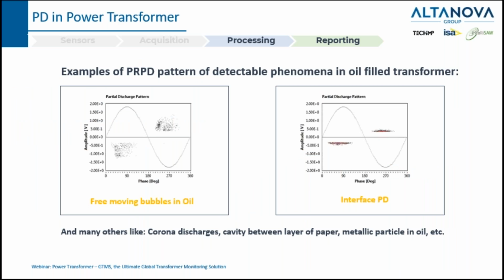For example, regarding power transformers, we can see here two typical PRPD patterns. On the left, you have an example of a pattern for a defect due to free moving bubbles, PD that can occur in bubbles in oil, and on the right, PD that can occur at the interface between two different layers of material with different dielectric strength. The name of this kind of PD is interface PD. We can have many other types of PD, like corona discharge, cavities between layers of paper, for example, or also metallic particles in oil.